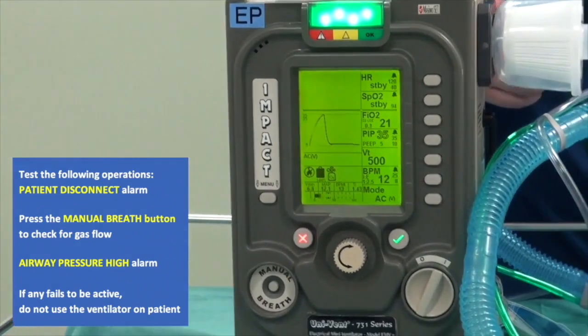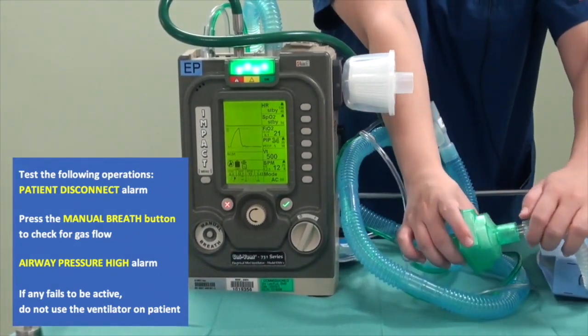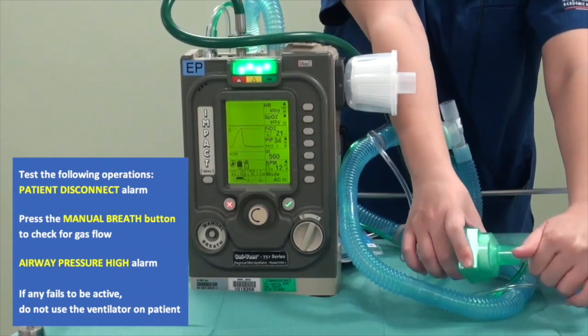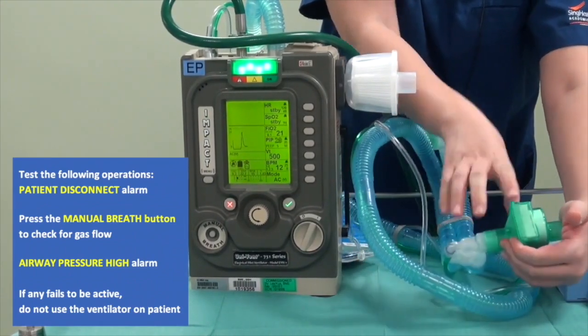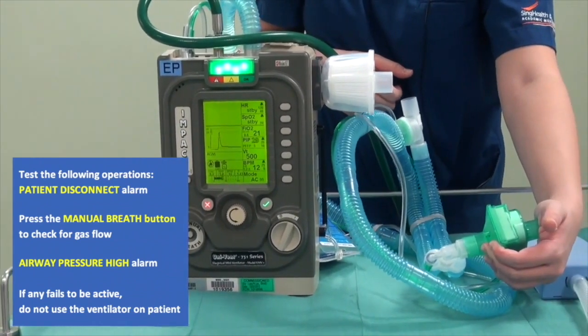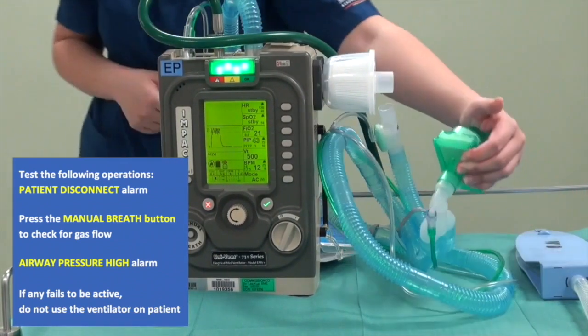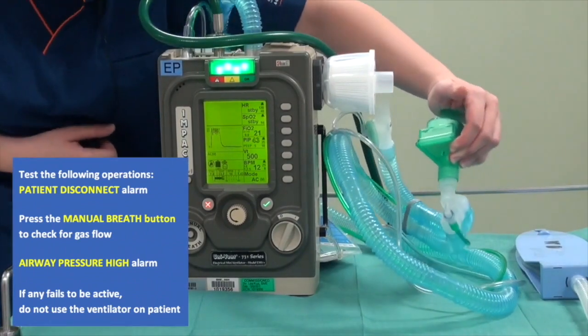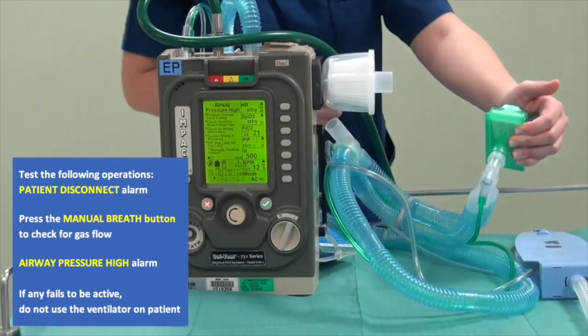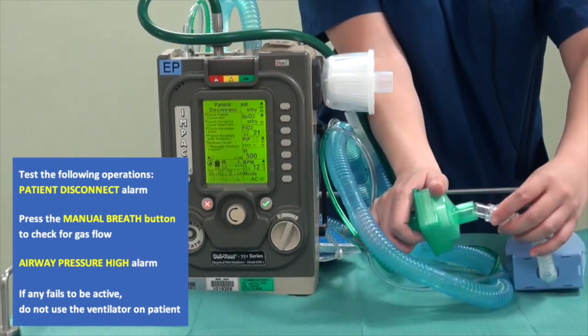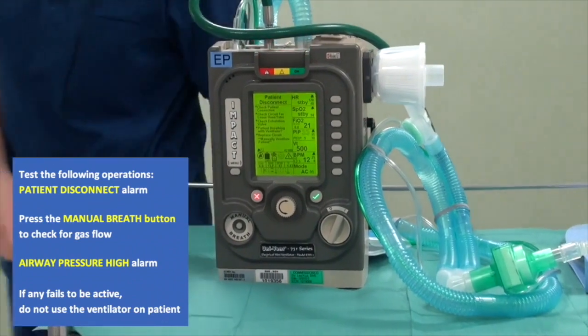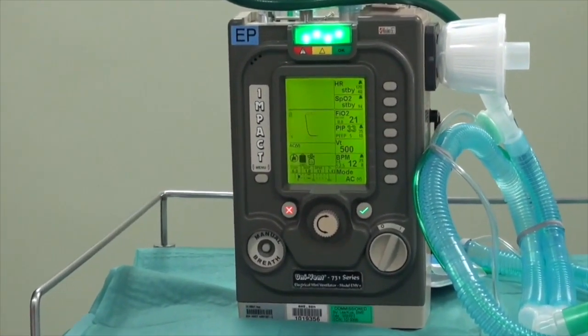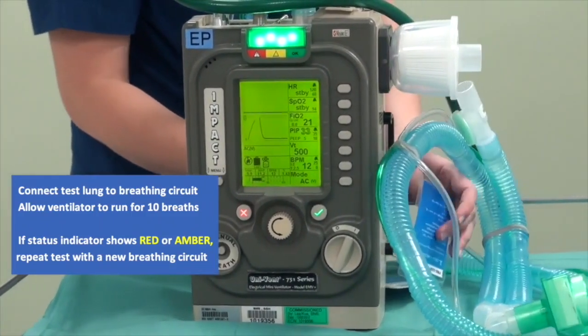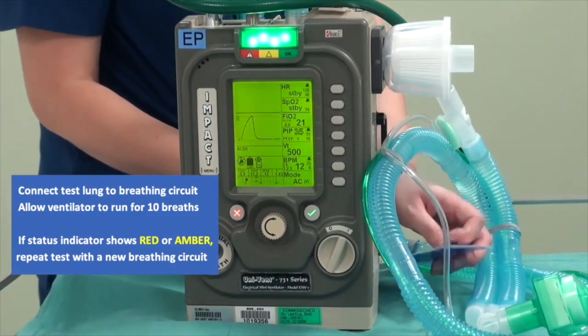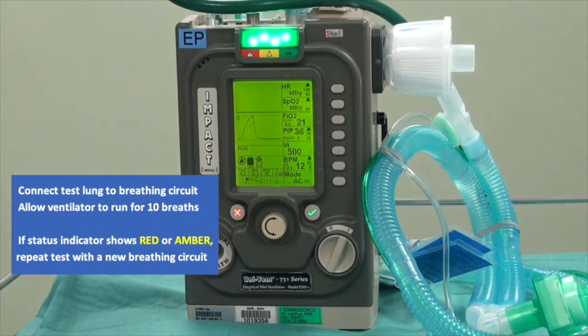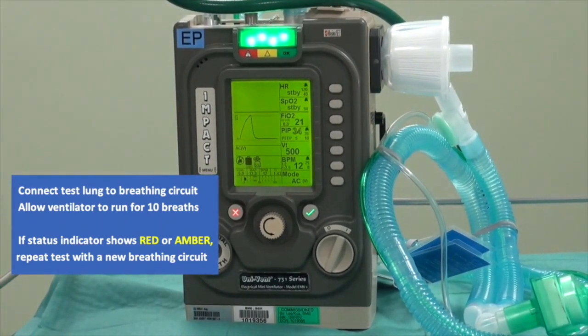Now I'll be testing the high airway pressure alarm using a gloved hand. Occlude the patient's end. High airway pressure alarm should come up. Once I release it and connect it to the test lung, the alarm should resolve by itself again. After that, I need to test the ventilator on 10 breaths. So after 10 breaths, if there are no red or amber alert alarms, the ventilator is safe to use on your patient.